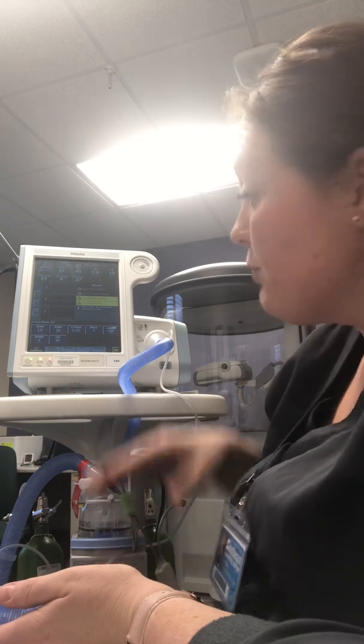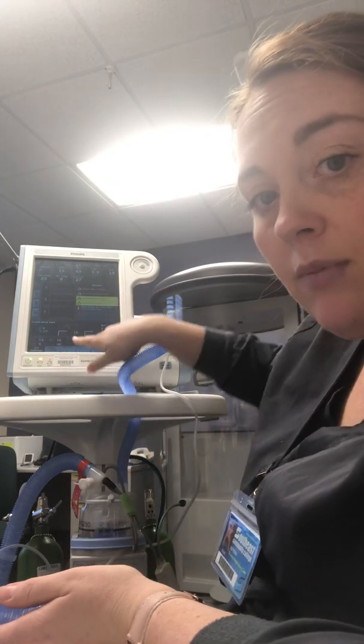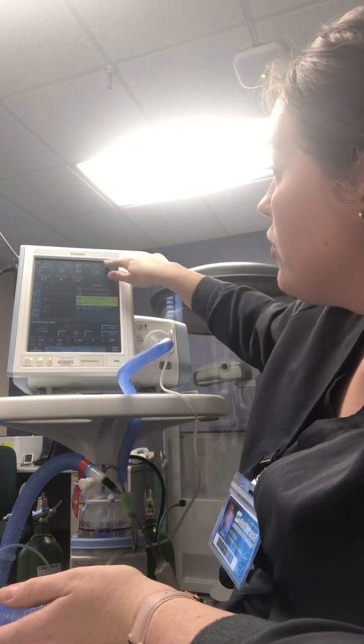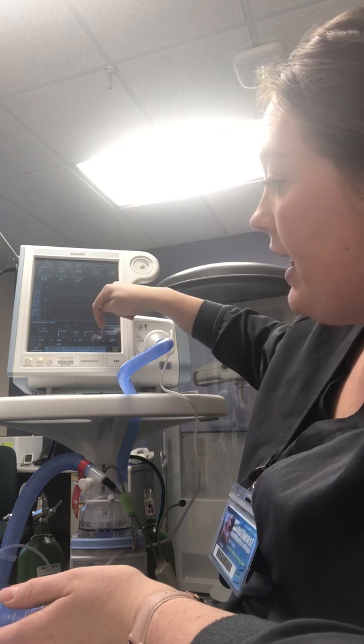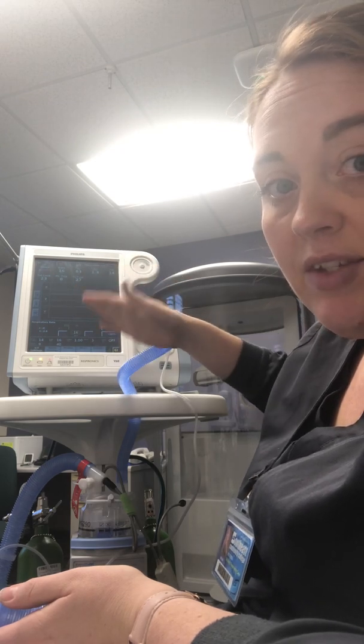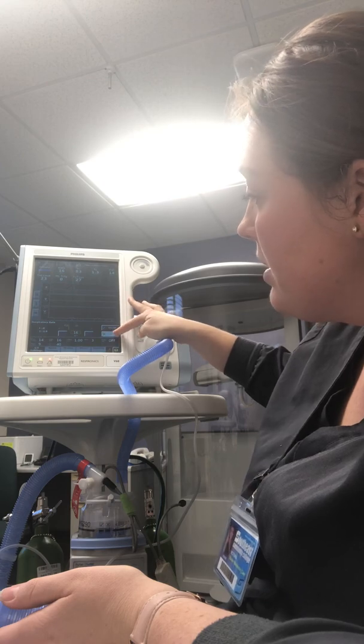So to change any of these parameters, all you do is click them, and then you have an arrow on either side. So you just adjust accordingly, and then once you've chosen the setting that you want, you just click accept. So that's how you change any of these settings. Now this particular type of ventilator, or this particular type of Bipap, can also be used in CPAP mode, which is just the one constant pressure throughout inspiration and expiration, and it could also be used in AVAPS mode. So it's kind of a multi-purpose type of machine.